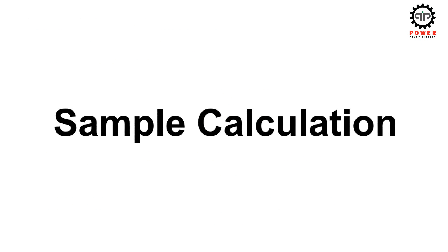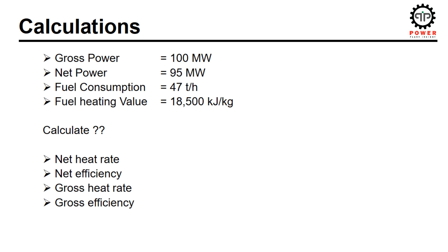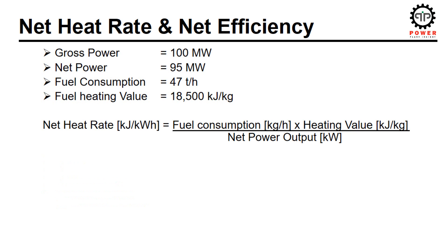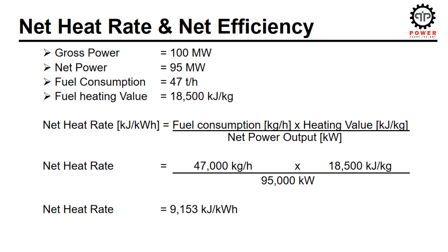Let us now apply all the concepts in a sample calculation. A power plant has a gross power output of 100 MW and a net power output of 95 MW — the balance of 5 MW is the house load. Fuel consumption is 47 tons per hour with a heating value of 18,500 kJ/kg. We need to calculate net heat rate, net efficiency, gross heat rate, and gross efficiency. Putting in the values of fuel consumption and heating value and dividing by net power, we get a net heat rate of 9153 kJ/kWh.